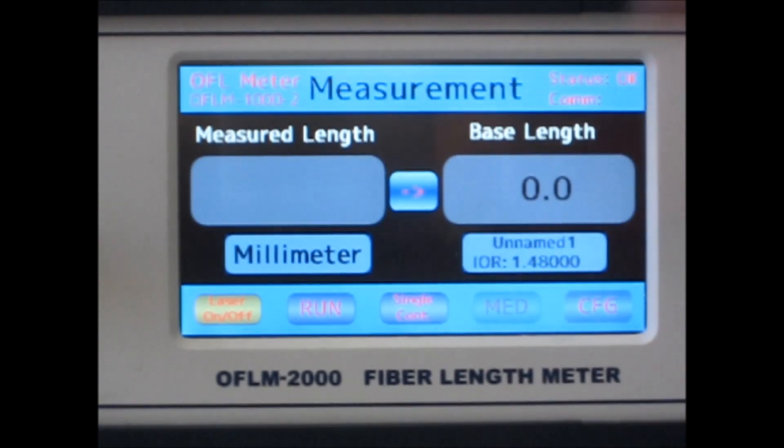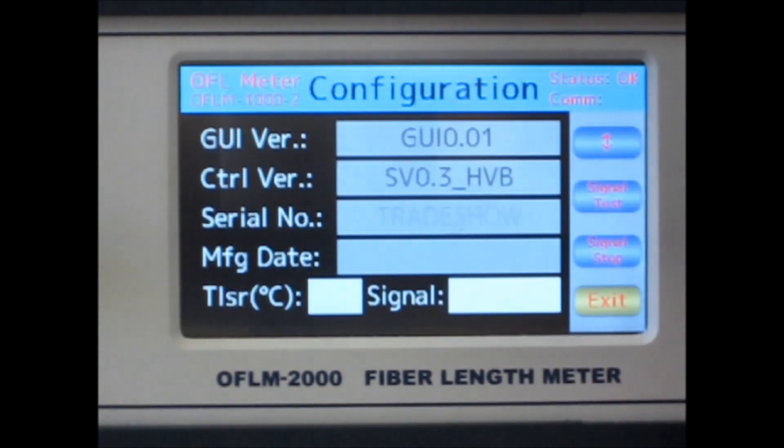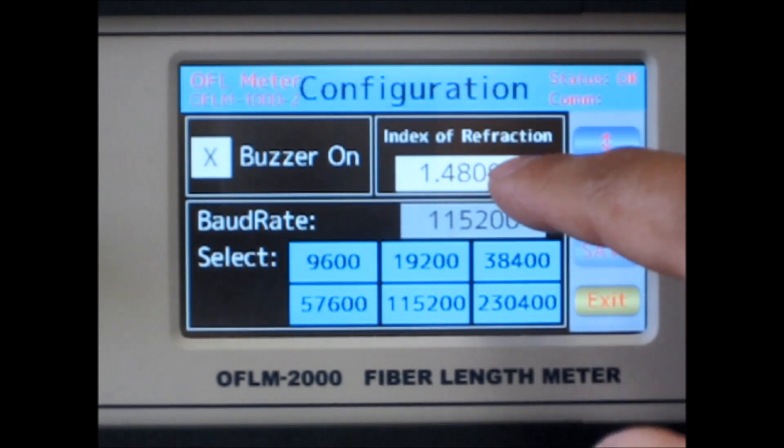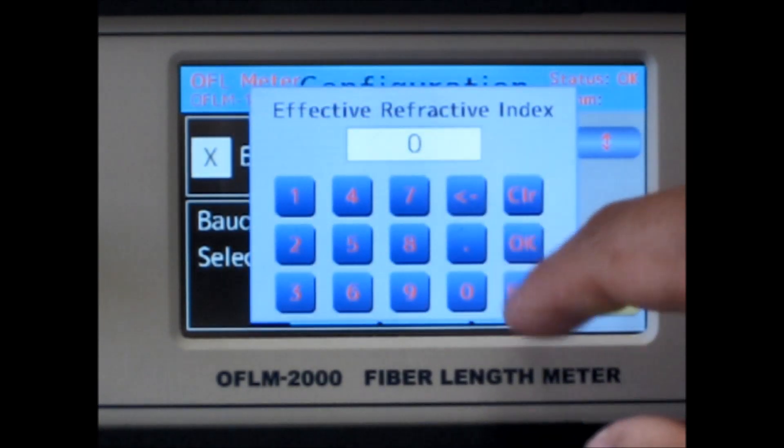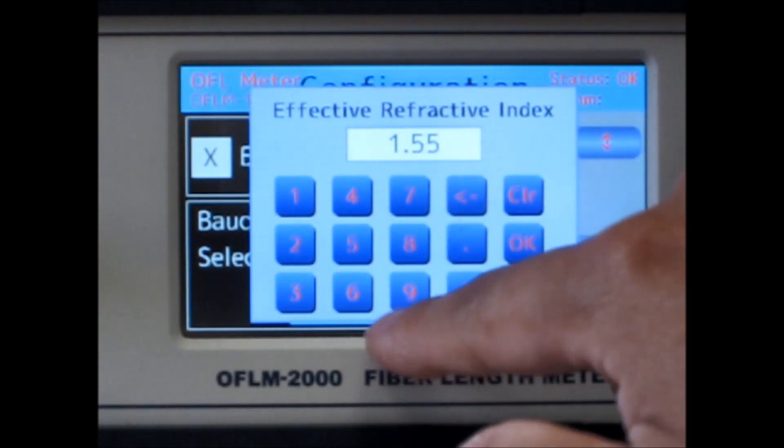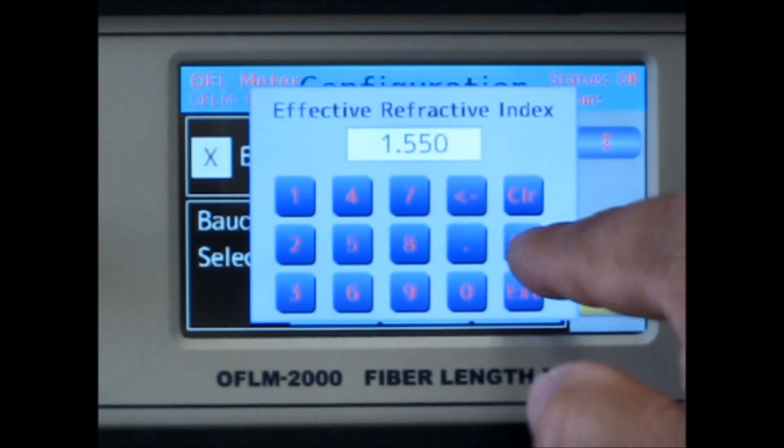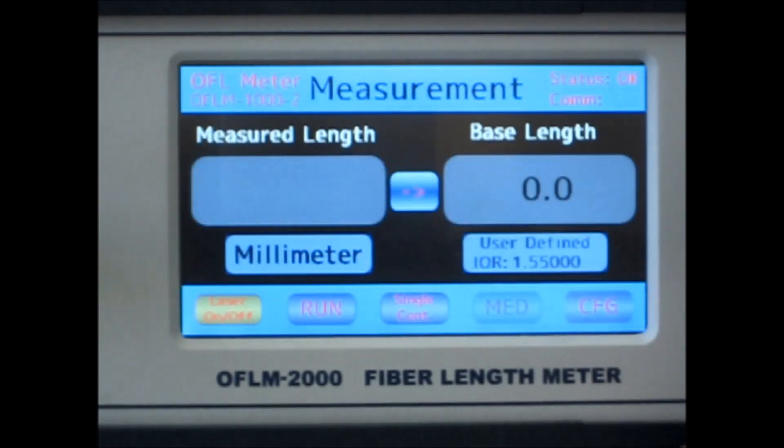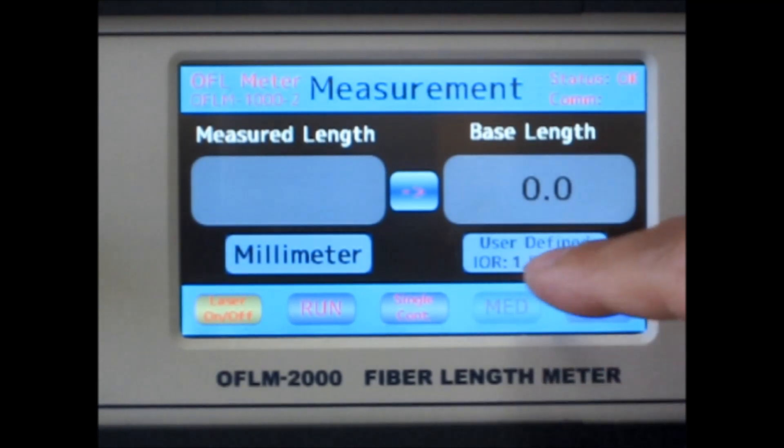You can also manually enter a specific index of refraction. To enter a custom value, push the rightmost configuration button. On the right side, push the topmost page change button. Tap on the index of refraction and you can type in a specific value. Push OK and save. Push the exit button to return back to the home screen. To change back to a standard value, just tap on the index of refraction and select the one.